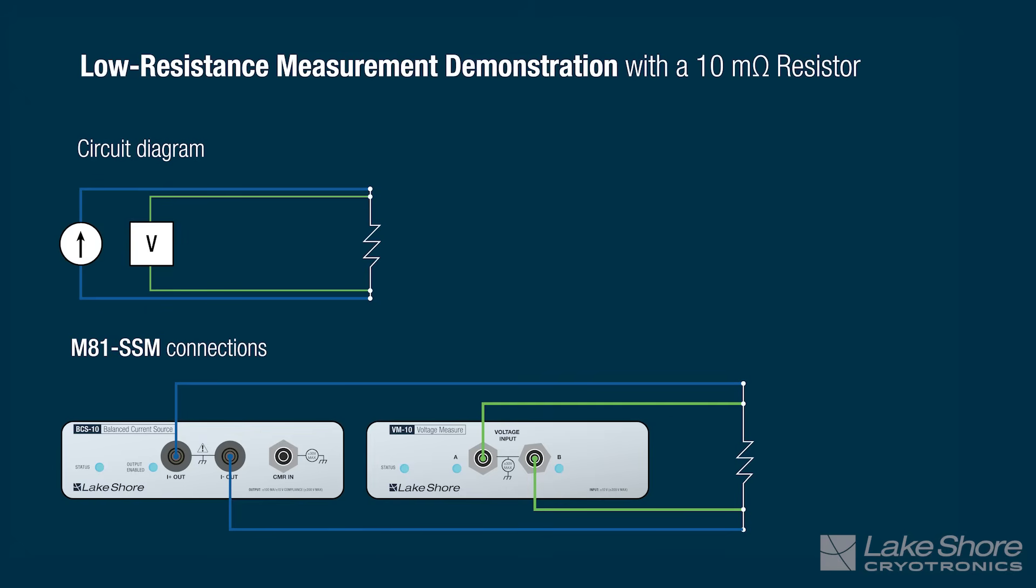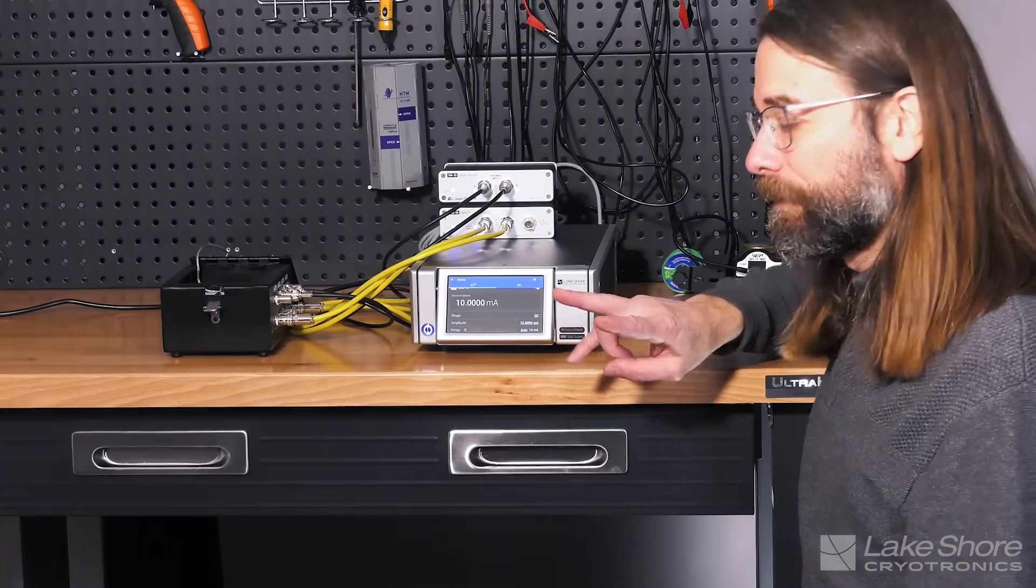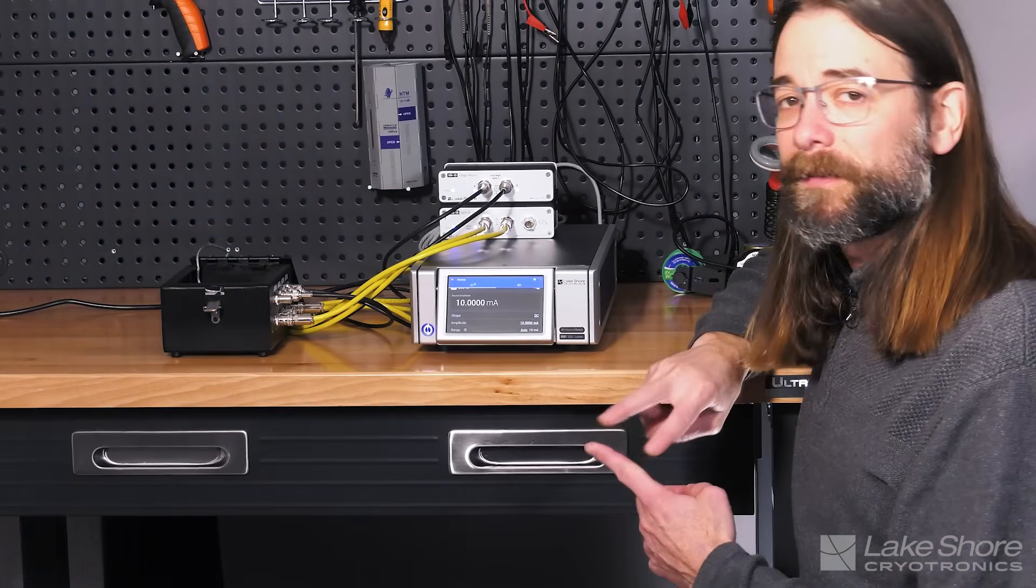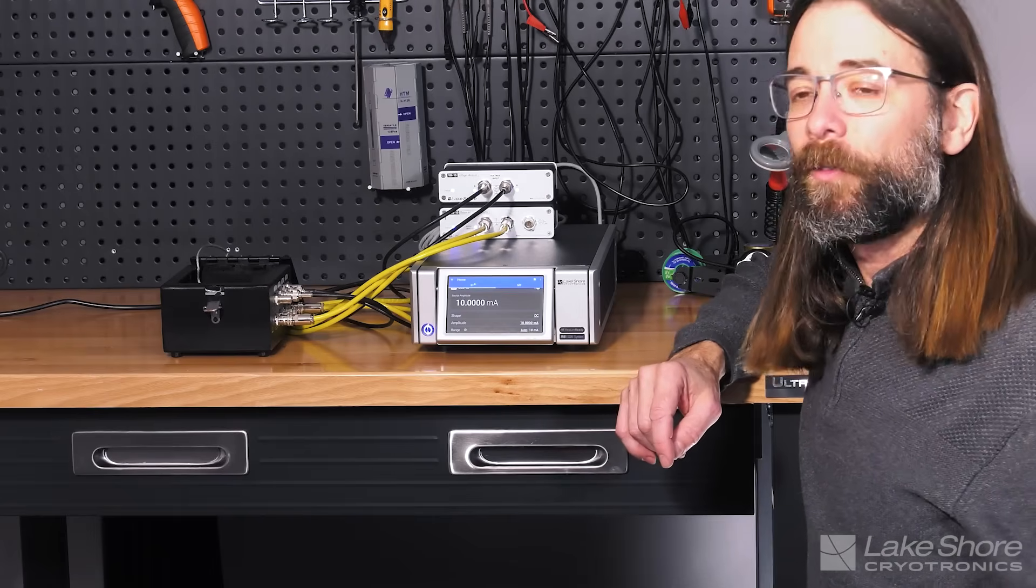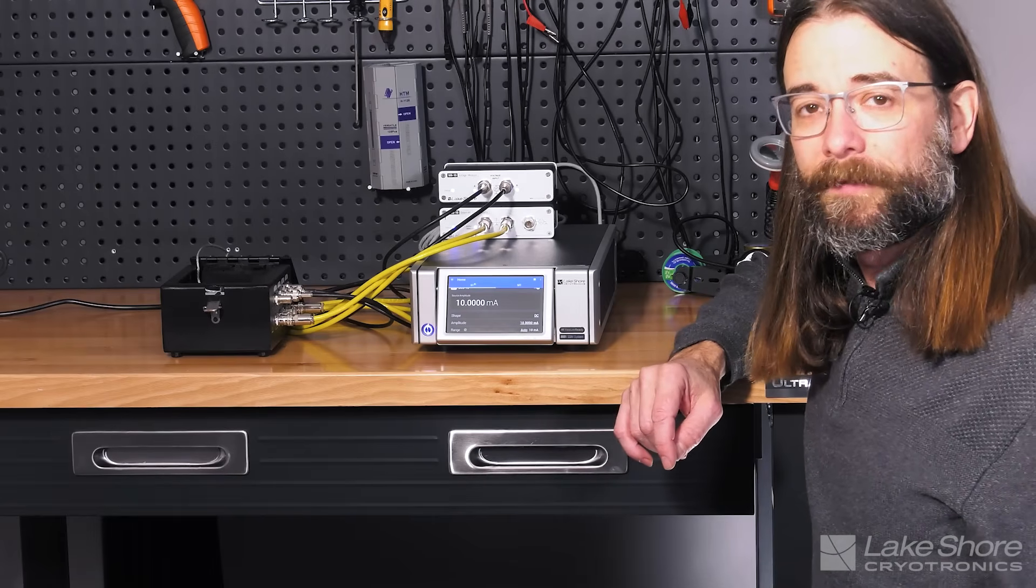We're going to be making a four-wire measurement. In a four-wire measurement, we're typically sourcing current and then measuring voltage as closely as we can to the device under test. And we're primarily doing that in order to minimize the resistance of the loss due to the resistance of the leads.